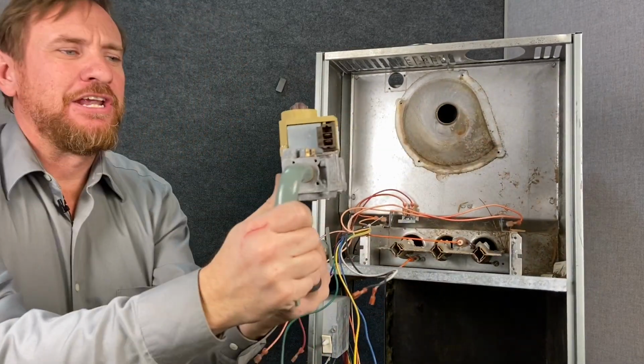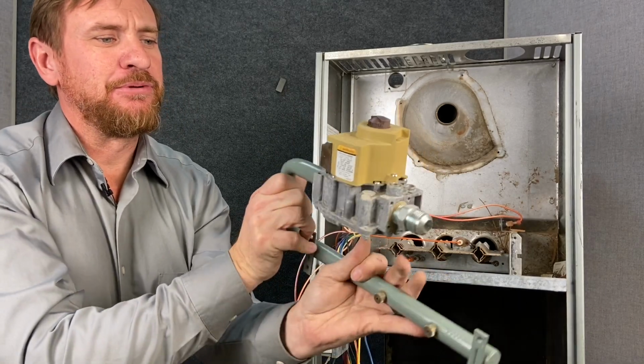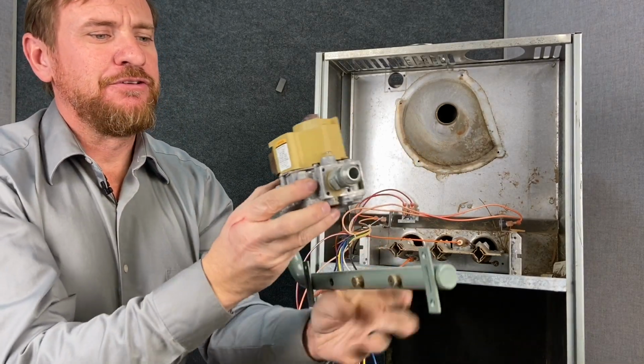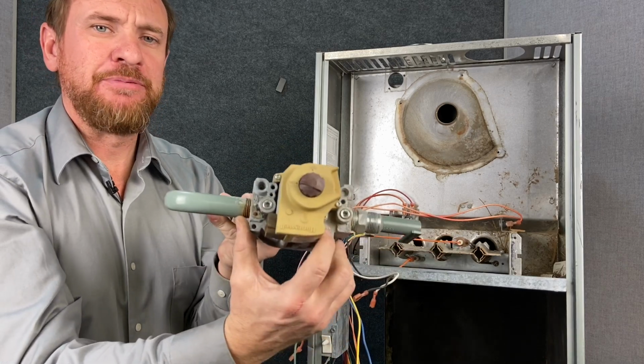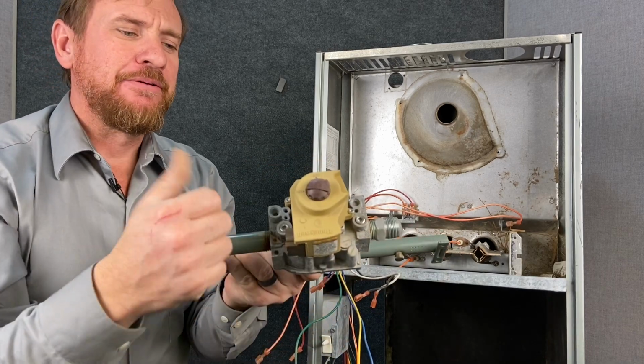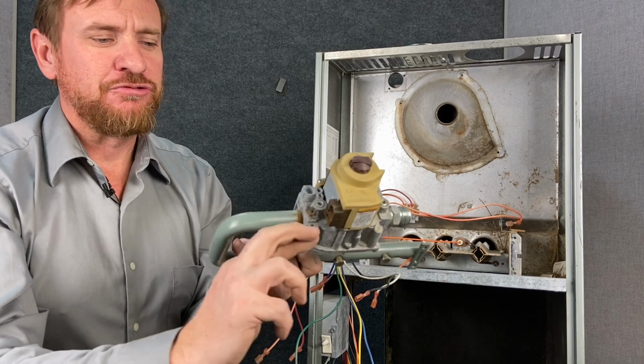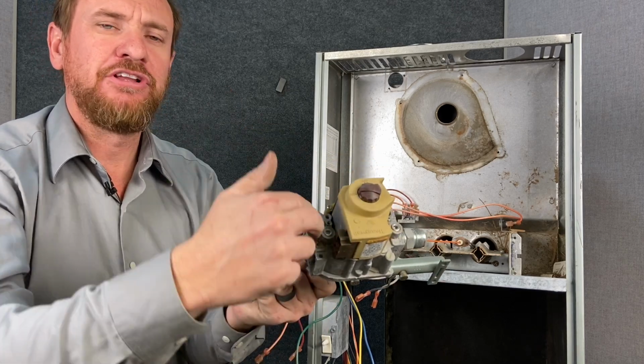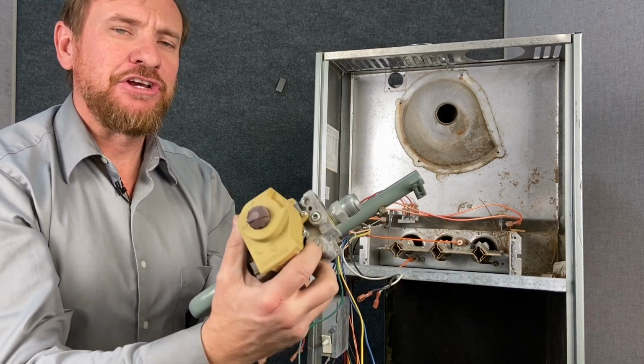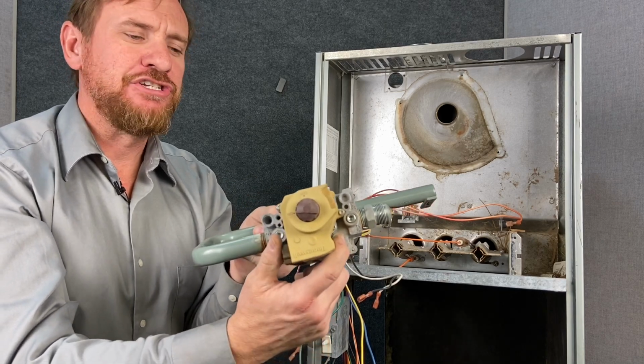Now we have our combination gas valve, which is a very simple component, and it's going to have a few little ports here. One is going to be the adjustment port for the gas pressure. It's a combination of a solenoid valve, which we have our low voltage in here that opens and closes, and secondly a pressure regulator. So behind this cap is how we adjust the pressure.